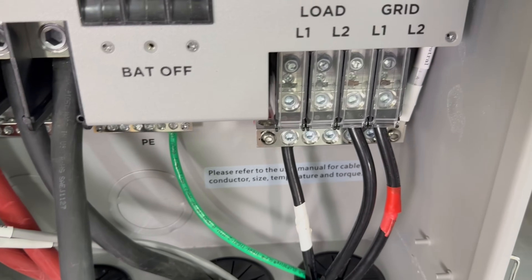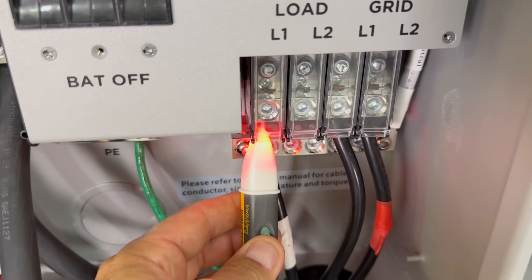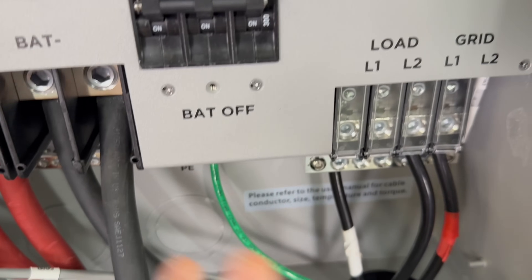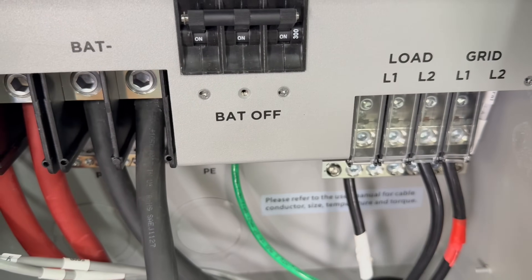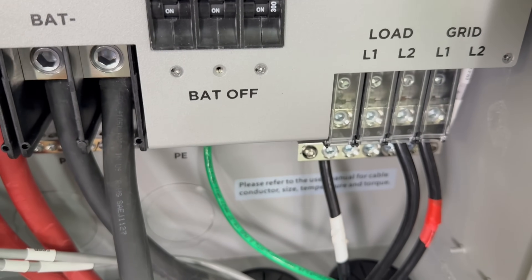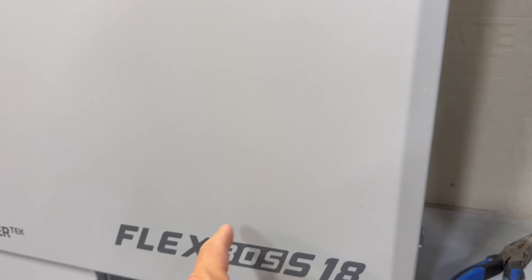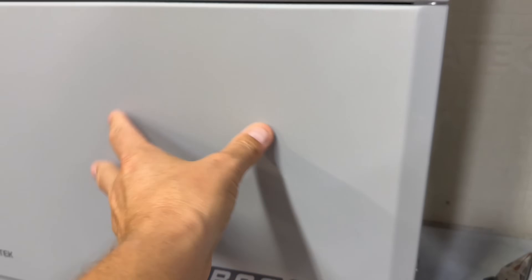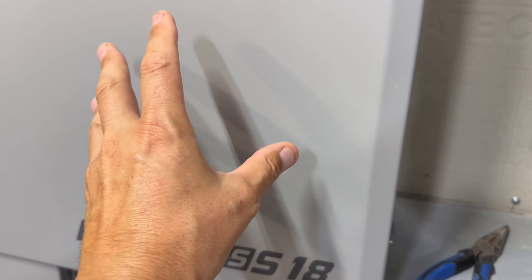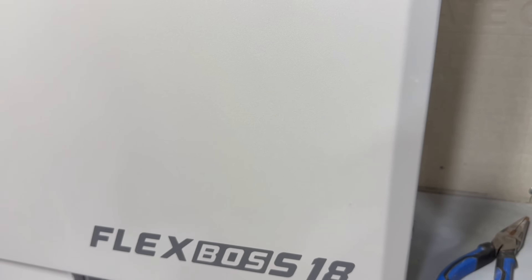I'll show you on the load port - it is hot. This is the FlexBOSS 18. You just don't have power here on the load ports normally, but even though it's considered in hybrid mode - because it is sending its power back from the grid port to the Grid Boss - you do have power here on these ports. Also, the output numbers probably aren't going to be accurate if you are powering anything from the load port, since all the info is supposed to be going through the Grid Boss. That's probably why they say it's not supported.